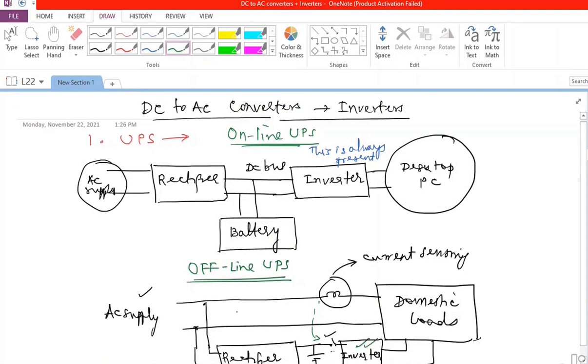Many home inverters follow this offline UPS configuration. For computers in data centers or life-support systems where no glitch is acceptable, only online UPS is used. Where a small glitch is tolerable, offline UPS may be used, and offline UPS is generally less expensive than online UPS, so it is preferred for non-critical applications.